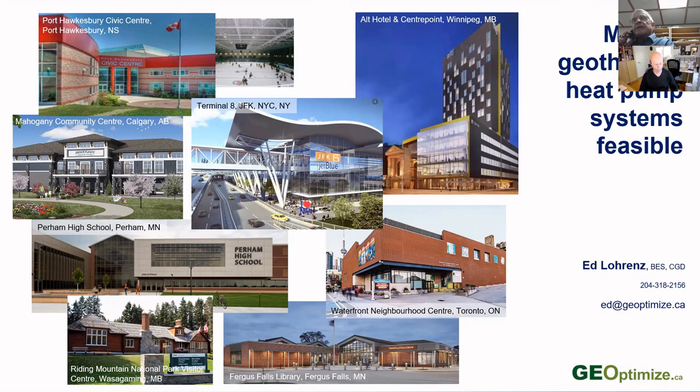If, for example, you're looking at a multifamily residential building and you've got a lot of excess heat, let's say a lot of condominium buildings with a glass curtain wall that absorb a lot more solar heat, they have to do a lot more cooling than heating. Using that to melt snow at the front entrance, for example, or a ramp to the basement parking lot would be a good thing. Adding the domestic hot water loads for the building to a building like that is a really big benefit. It provides domestic hot water, eliminates the use of gas for making hot water, and actually can reduce the size of the ground heat exchanger as well as improve the long-term performance of it.